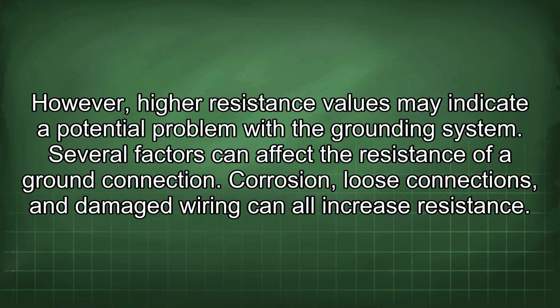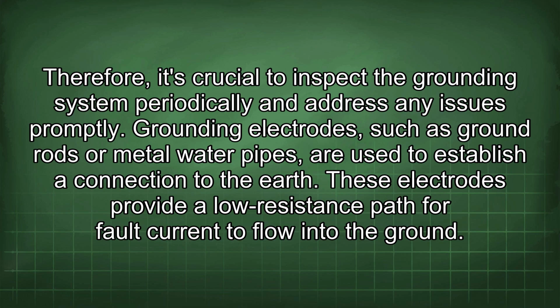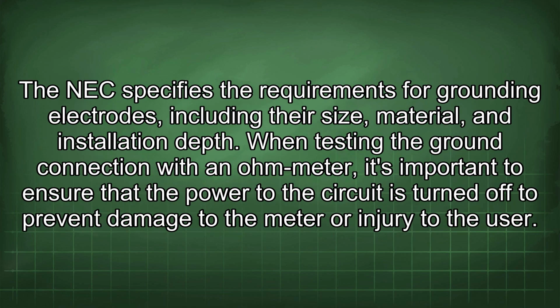Several factors can affect the resistance of a ground connection. Corrosion, loose connections, and damaged wiring can all increase resistance. Therefore, it's crucial to inspect the grounding system periodically and address any issues promptly. Grounding electrodes, such as ground rods or metal water pipes, are used to establish a connection to the earth. These electrodes provide a low resistance path for fault current to flow into the ground. The NEC specifies the requirements for grounding electrodes, including their size, material, and installation depth.